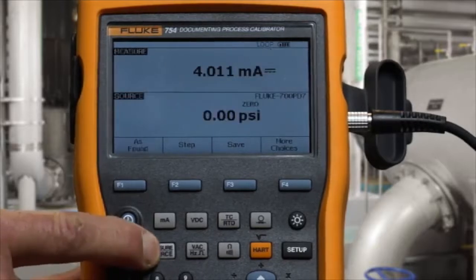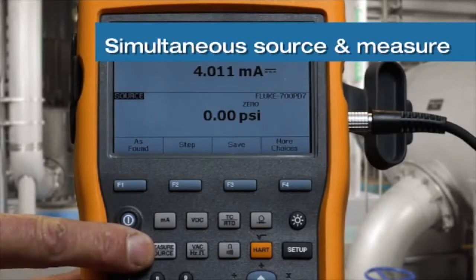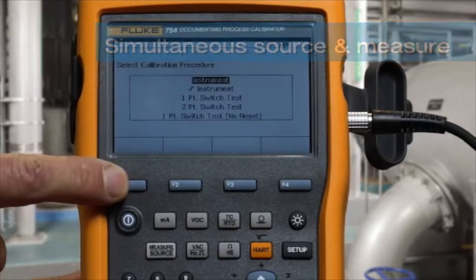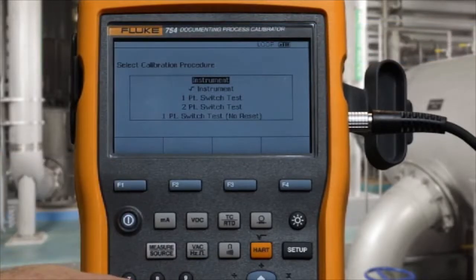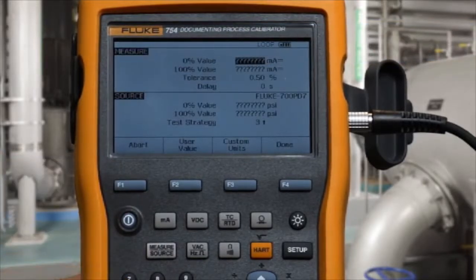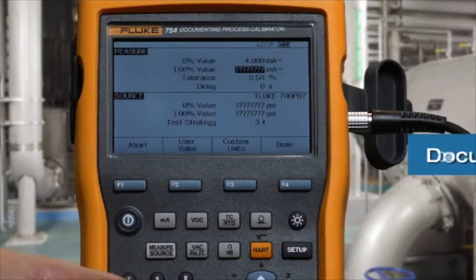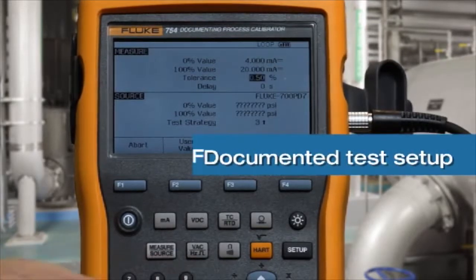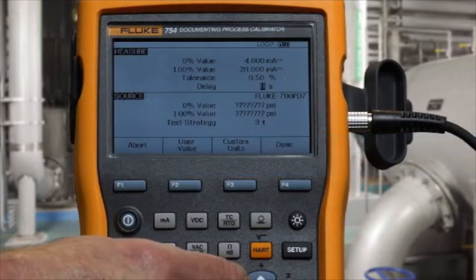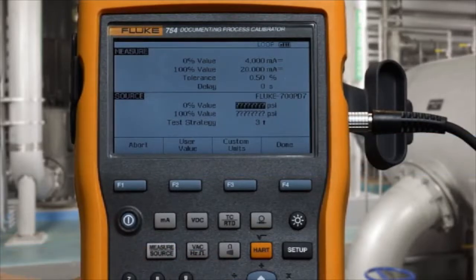Next, we go to the split screen to do calibration. Select as found for an instrument. We're going to measure 4 to 20 milliamps to a test tolerance of 0.5%, and we're going to source 0 to 100 psi, and we're going to do a 3-point test.